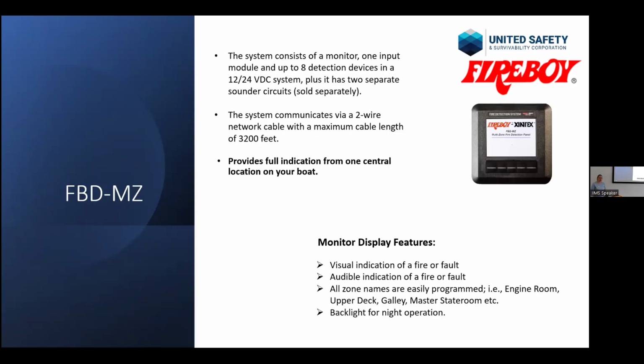If you need a little bit more than 2 zones, this one monitors 4 or 12 zones. Very simple use. It's got an LCD display, comes with a separate I/O unit, and if you're a bit tech savvy yourself, you can decide how many zones you want to see. You can program yourself the text for each zone. So you can say this detector zone 1 galley, zone 2, I don't know, main cabin. And you can change the settings just by using a text file. You write it as a text file and plug it in with the USB in the back of the input unit.